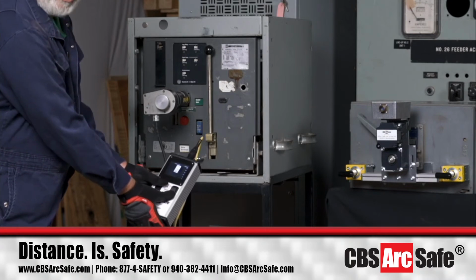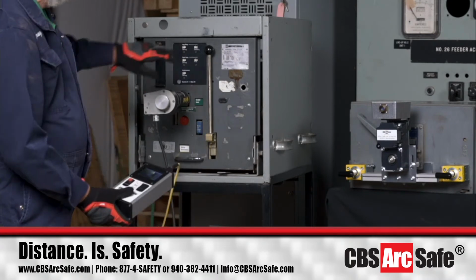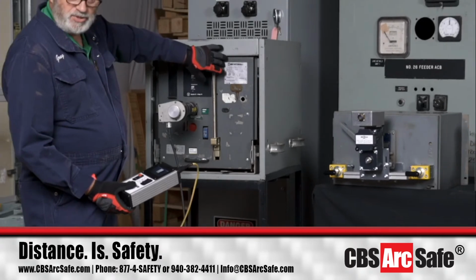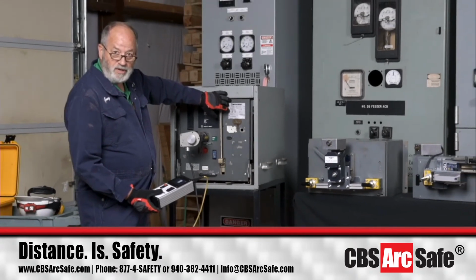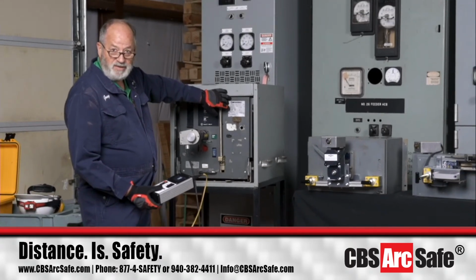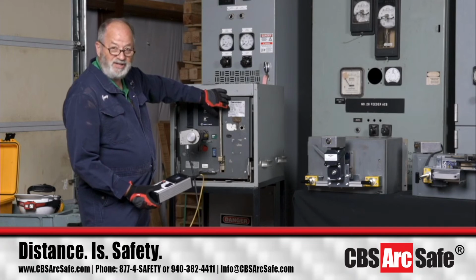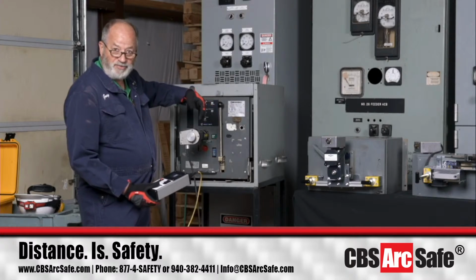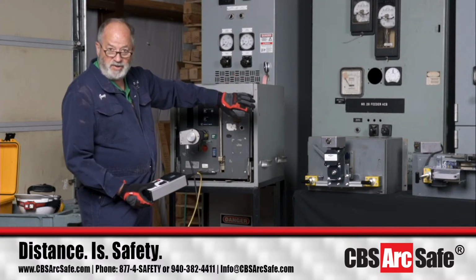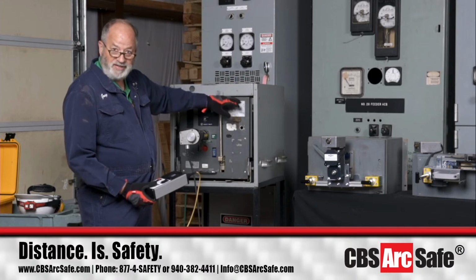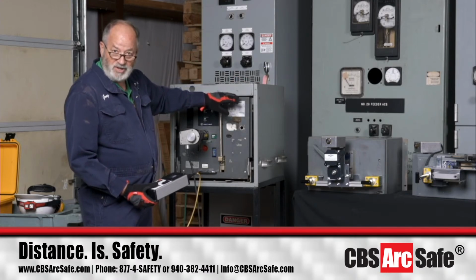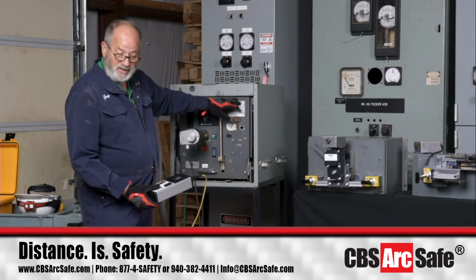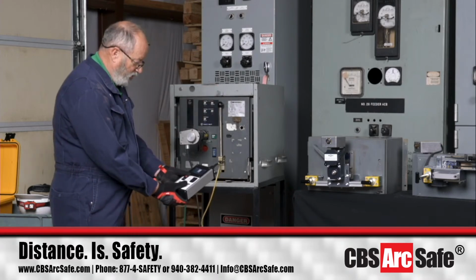And it releases the torque at the end of the process. Now, you'll notice that this DS breaker actually has a SquareD logo on it. The DS breaker was originally designed by Westinghouse in 1967 and introduced to the market. It became commercially available in 1969. So I don't know how far from 1969 on SquareD had a license to make them, but you will find these that say SquareD on them versus Westinghouse or Eaton Cutler Hammer, and it was a licensed breaker made by them. So we're going to now rack the breaker back in.